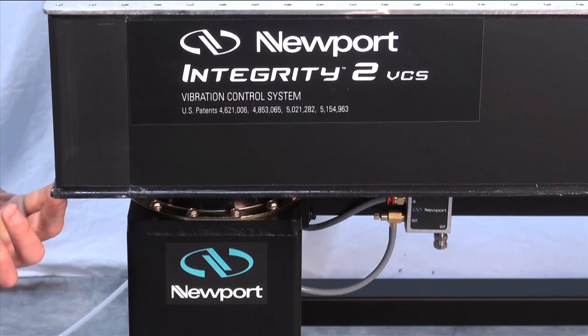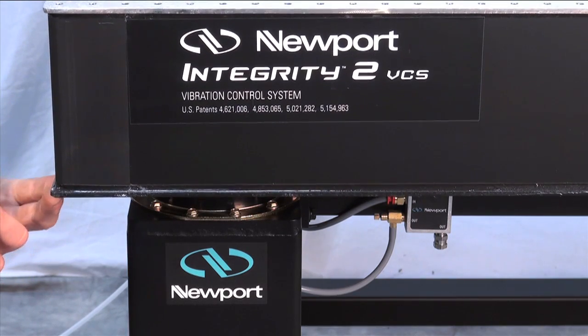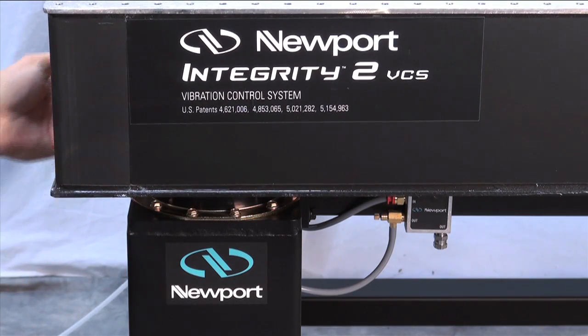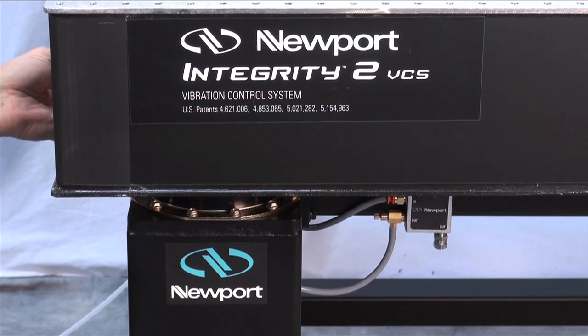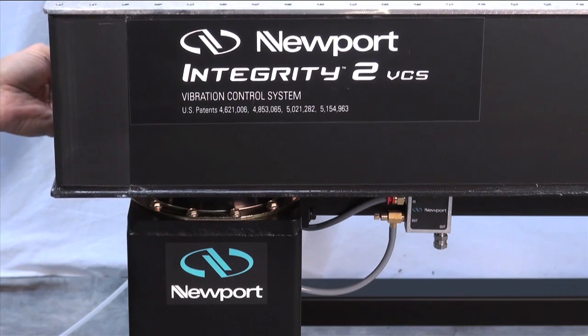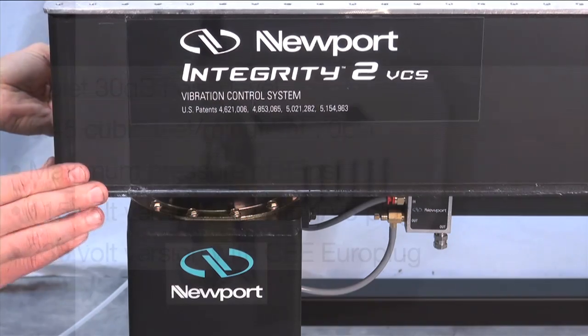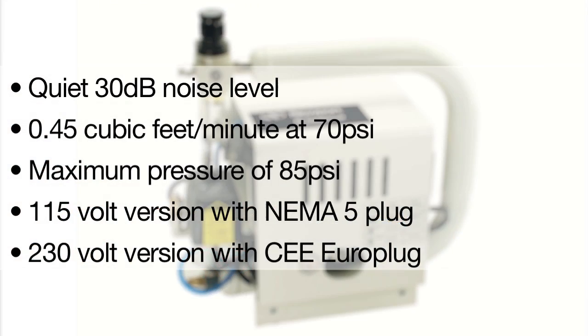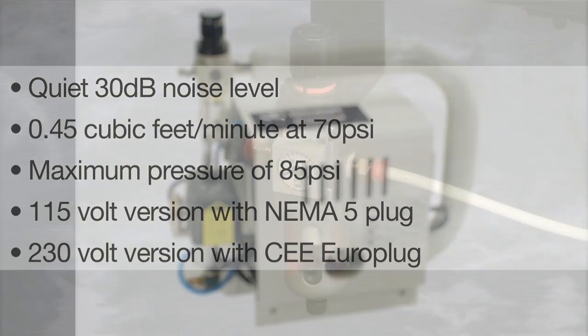The ACWS air compressor features a smaller footprint, lighter weight, and an ultra-quiet 30 decibel operating noise level for use in sensitive lab environments. It can supply over 0.45 cubic feet per minute of air at 70 psi and has a maximum pressure rating of 85 psi, more than enough to support an Integrity VCS system.